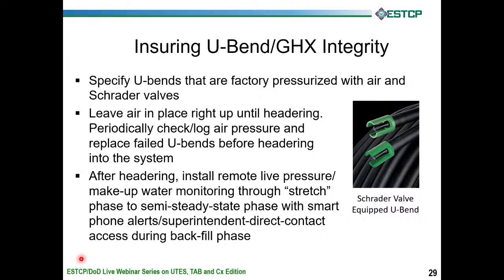We like to use the U-bends that we've talked about before that go down into the ground, that are in essence the heat exchanger that's pulling heat into or out of the earth. We like to buy those with Schrader valves pre-installed and pre-charged with air. So there's a certain charge they come from the factory with, and if you've had to sit through a fluids class or physics, you know that the temperature and pressure vary with a gas. As the temperature goes up, the pressure goes up. So the pressure will vary some, but you have them shipped from the factory at a certain charge.